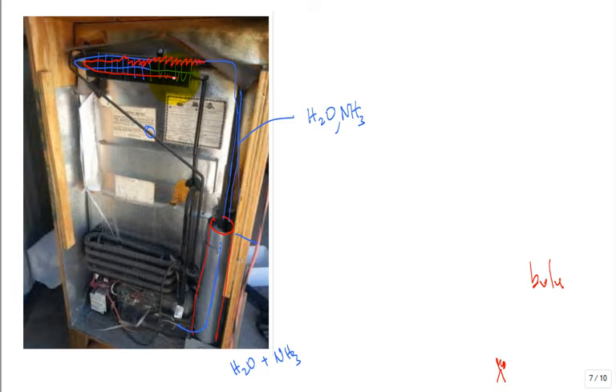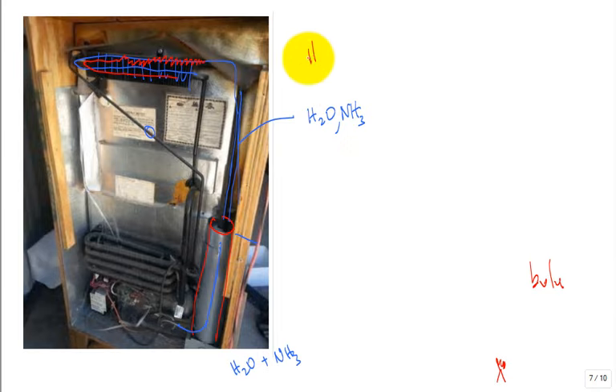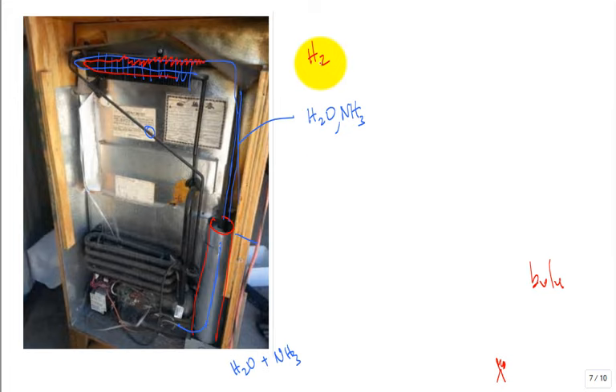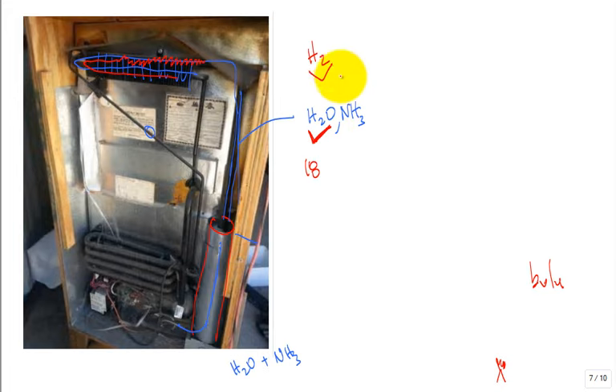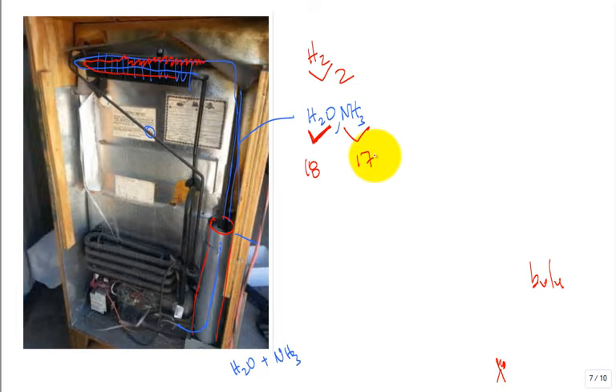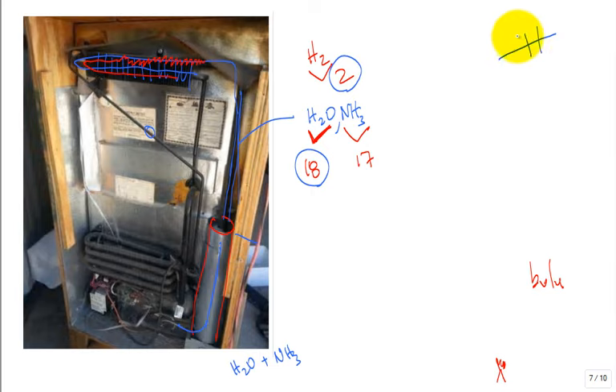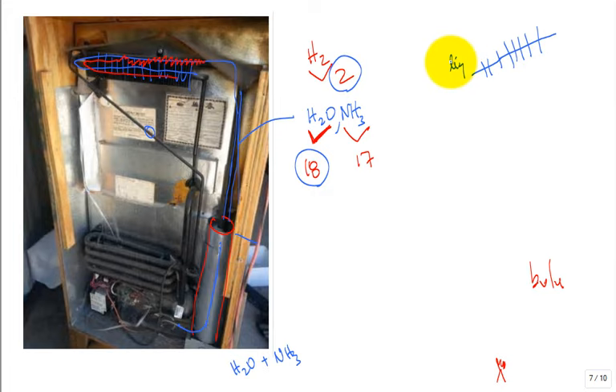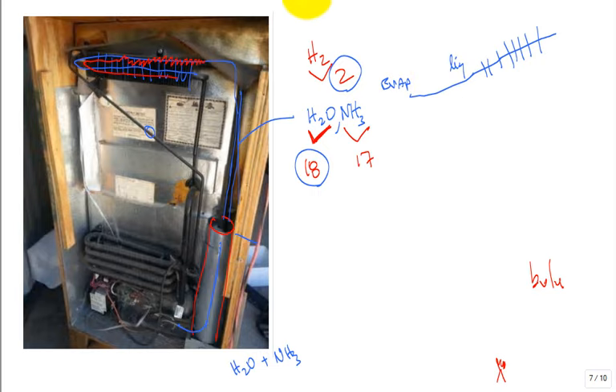You introduce another gas, hydrogen H2. This gives me a headache trying to describe it. You have water, ammonia, and hydrogen H2 in this system. Tell me about the molar mass of water: 18. Molar mass of hydrogen: 2. And ammonia: 17. Very good. You come out of the finned condenser, it came in vapor, it all comes out as liquid ammonia.